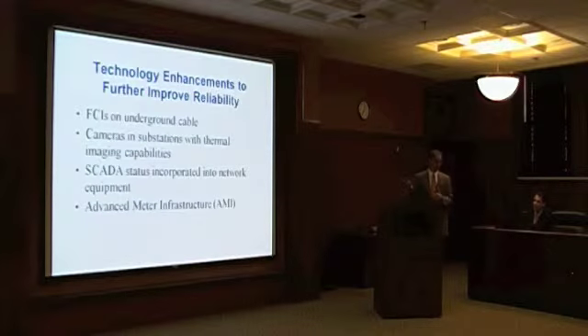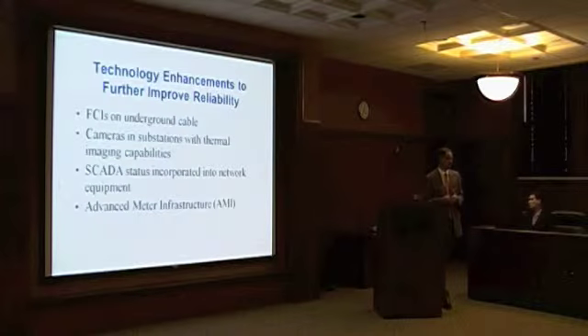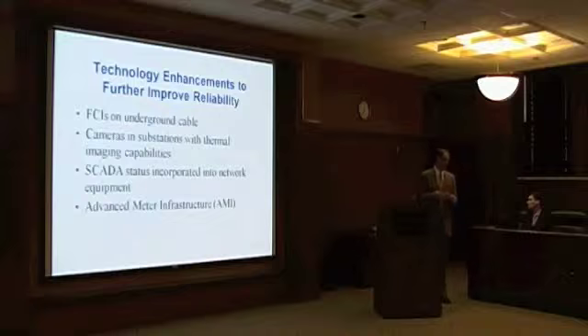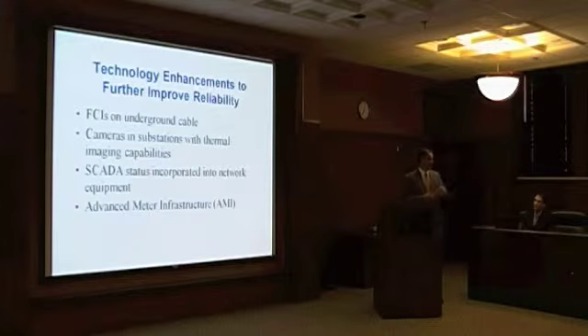On the underground system, it takes much, much longer to isolate where your problem is. The good news is, in most of our areas, we have a loop system, so once we find that damaged area, we can do some backfeeding to restore power as quickly as possible to those customers. But there are some new devices available, faulted circuit indicators for underground systems. So what we now have on the overhead system, we can have on the underground system at manholes or switchgear to help us quickly identify that bad cable section.